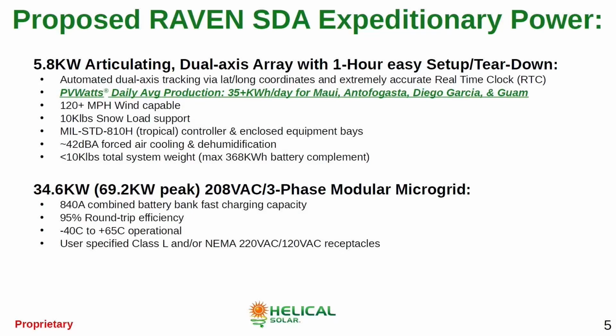It should be about 42 dBA of external noise when the fans are running, and it will have 34.6 kilowatts of nominal power with a 69.2 kilowatt peak running 208 volts 3-phase. And we'll be able to add in Class L and NEMA receptacles for user requirements. Next.